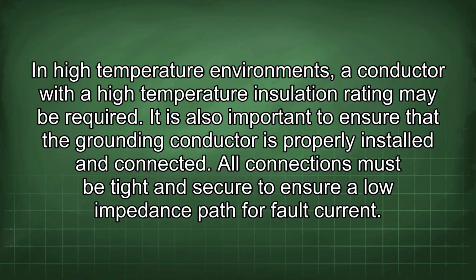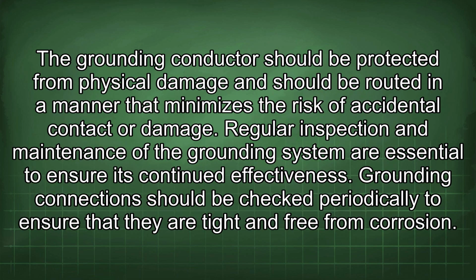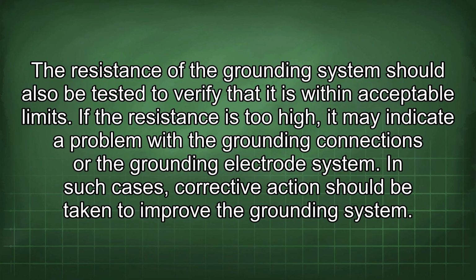It is also important to ensure that the grounding conductor is properly installed and connected. All connections must be tight and secure to ensure a low impedance path for fault current. The grounding conductor should be protected from physical damage and should be routed in a manner that minimizes the risk of accidental contact or damage. Regular inspection and maintenance of the grounding system are essential to ensure its continued effectiveness. Grounding connections should be checked periodically to ensure that they are tight and free from corrosion. The resistance of the grounding system should also be tested to verify that it is within acceptable limits. If the resistance is too high, it may indicate a problem with the grounding connections or the grounding electrode system. In such cases, corrective action should be taken to improve the grounding system.